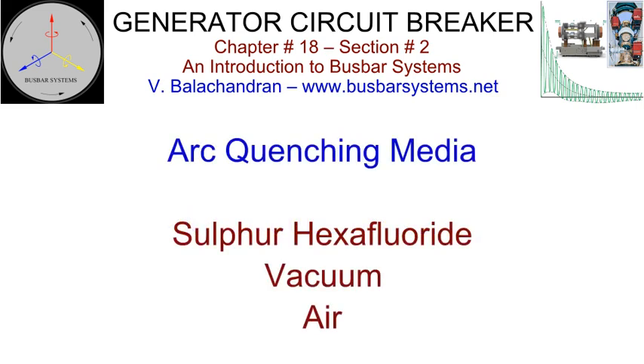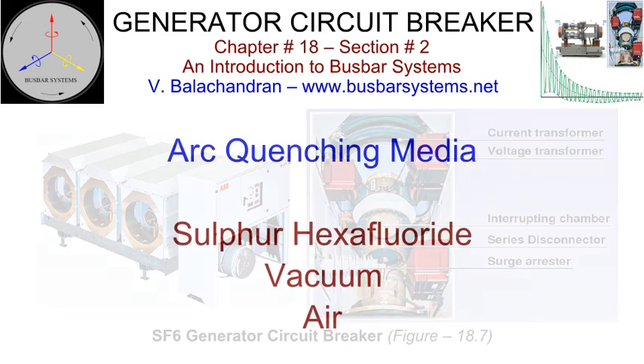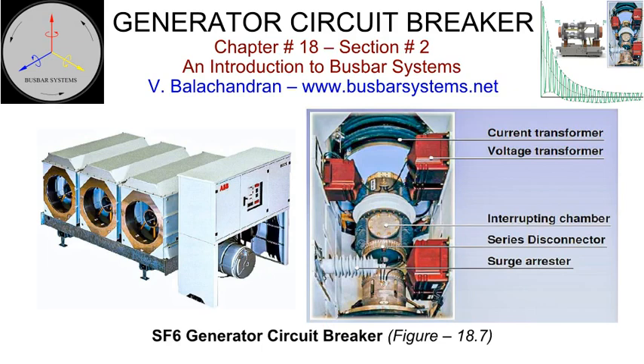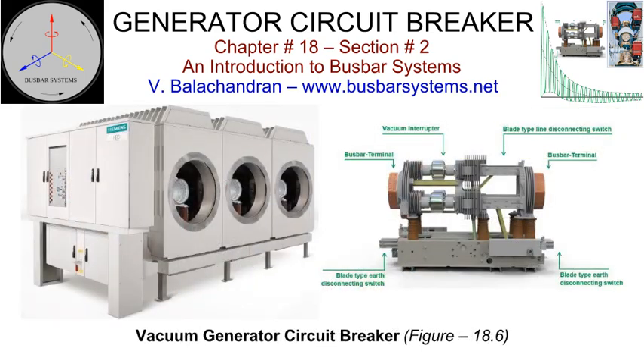Sulfur hexafluoride, vacuum, and air blast have been used as arc quenching media in generator circuit breakers. Generator circuit breakers with sulfur hexafluoride as the quenching media are most widely used. These have a continuous current rating of up to 25 kilo amperes under natural air cooling, and 50 kilo amperes under forced air cooling, up to a voltage rating of 36 kilo volts. This is almost in line with the isolated phase bus philosophy, where the isolated phase bus rated above 25 kilo amperes seems to be more economical and practical with forced cooling. Vacuum has been used as a quenching media for continuous ratings up to 15 kilo amperes, up to a rated voltage of 24 kilo volts. Vacuum interrupters are connected in parallel in each pole to achieve the specified rated current.